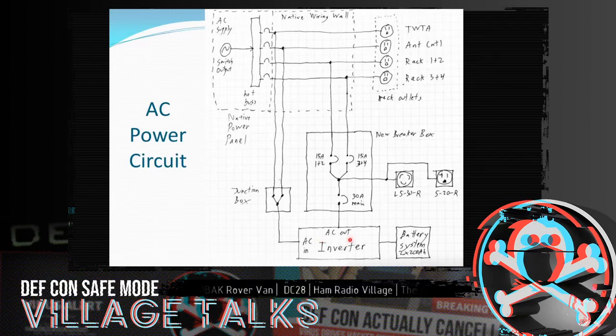The output of the inverter would go through a new 30 amp circuit breaker and then branch off into two of the racks for an existing 15 amp circuit, and another existing 15 amp circuit for the other two racks. Lastly, I installed two new sockets for higher current AC supply.